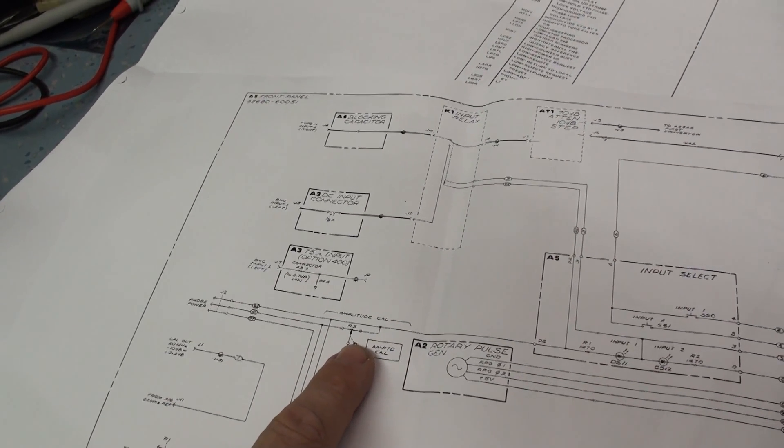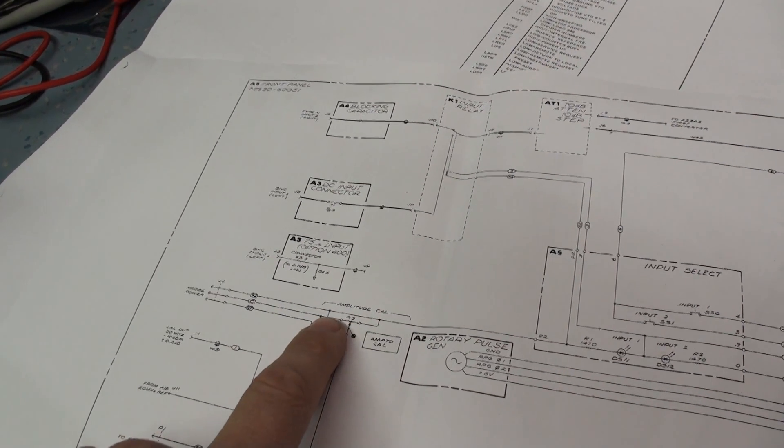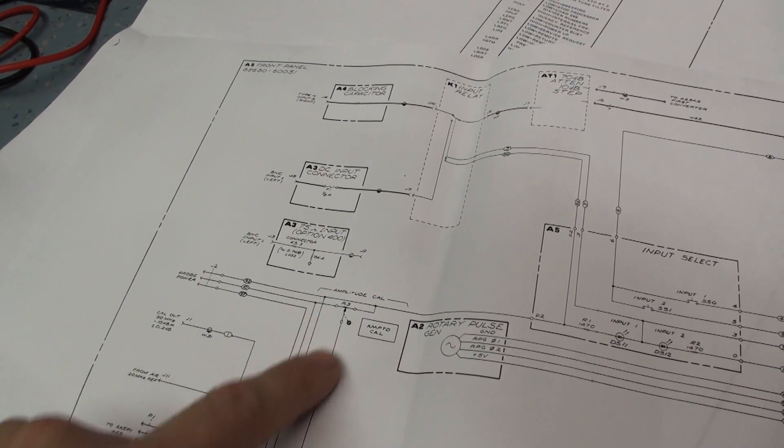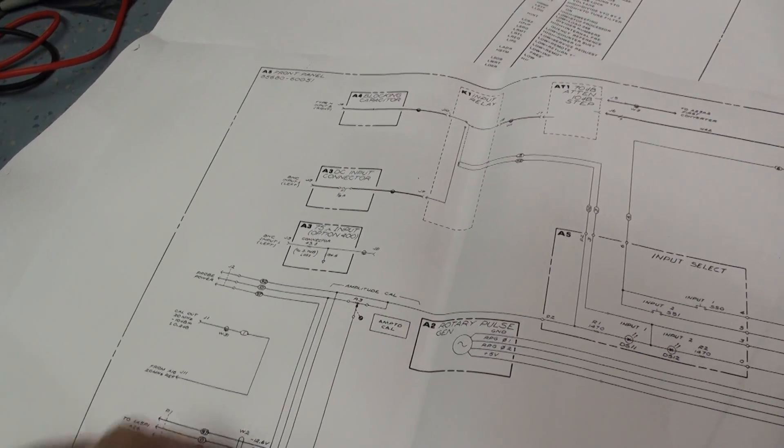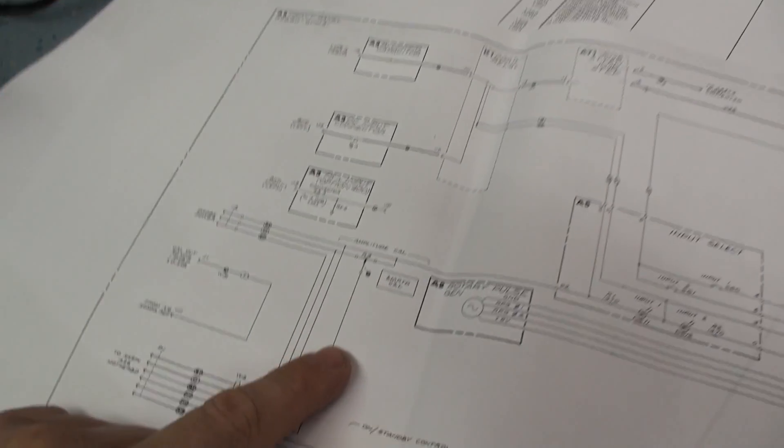So basically all this pot does, is this side of the pot's connected to ground. This side of the pot is connected to a plus 15 supply. And this is the centre wiper. It goes off to reference level, and that feeds off to the motherboard. So basically what that does is it goes from 0 to 15 volts, depending on the position of the pot. So that's fairly straightforward. So basically all that is, is a programmable voltage.